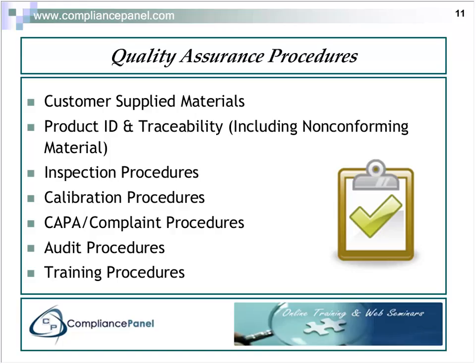Some of your inspection and test processes may be so complex that you can't test for everything, but you can make sure that you have proven that this test procedure, this test software for automated testing, has been validated and meets all the requirements necessary to prove that the product being tested was tested properly.